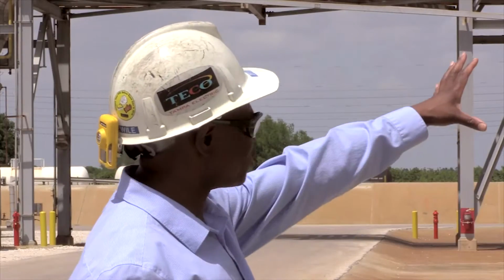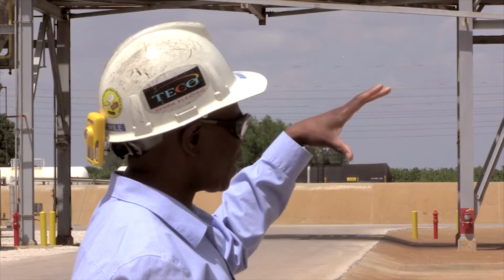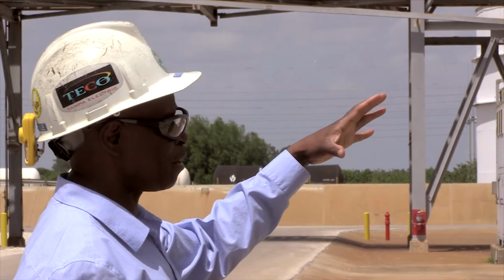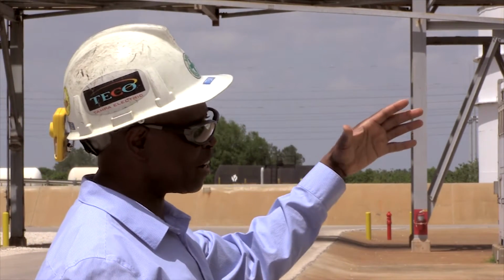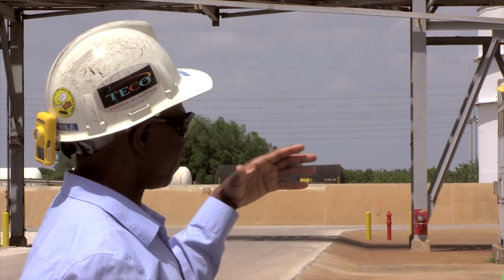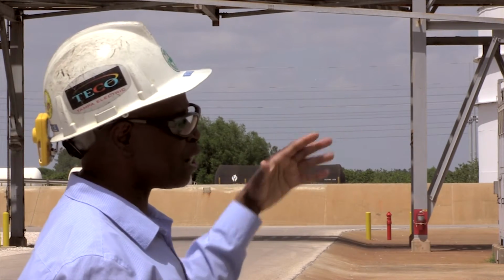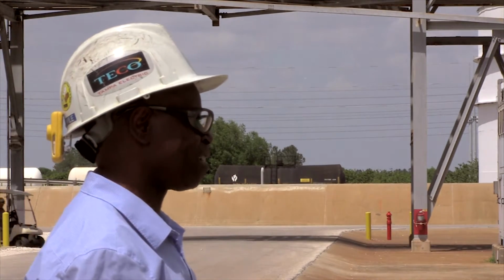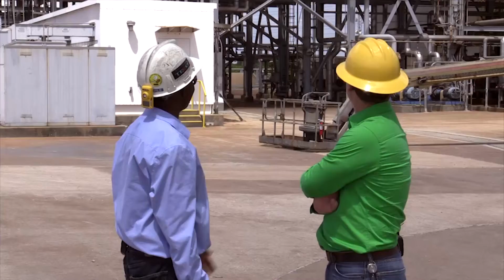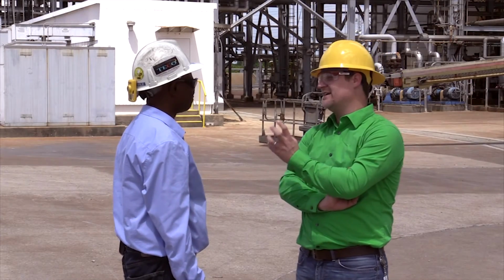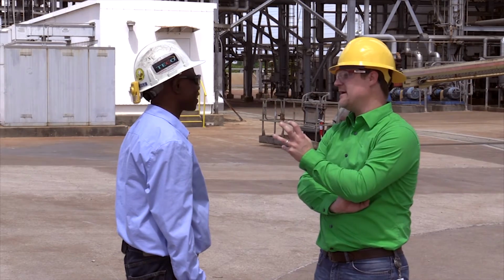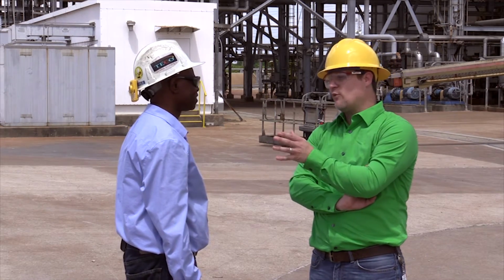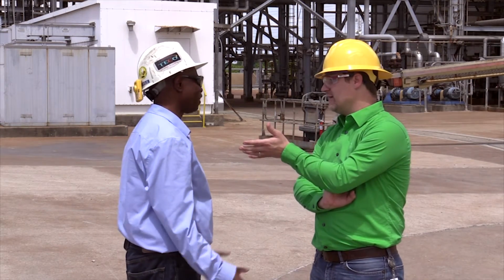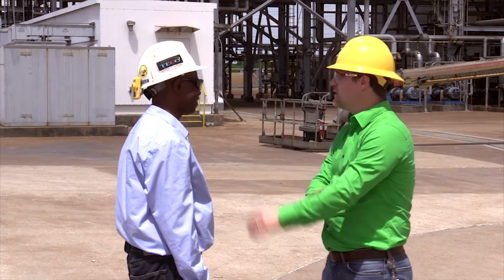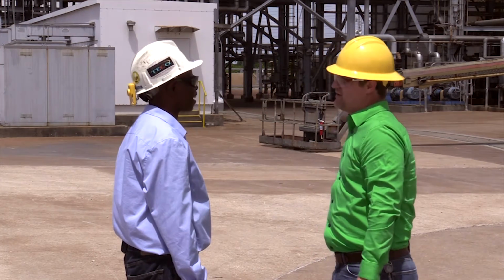So this is the heat recovery steam generator. Once the gases have been burned, the fuel gases, carbon monoxide and hydrogen, the exhaust gas is hot, coming out at about 1,000 degrees Fahrenheit. That heat is used to make steam. It's hard to imagine that kind of heat, when you figure boiling water is 212 degrees, and you're boiling it to 1,000 degrees.